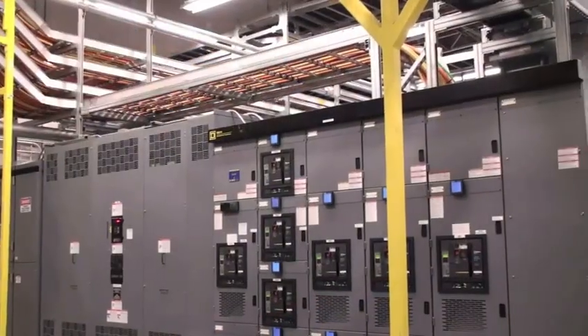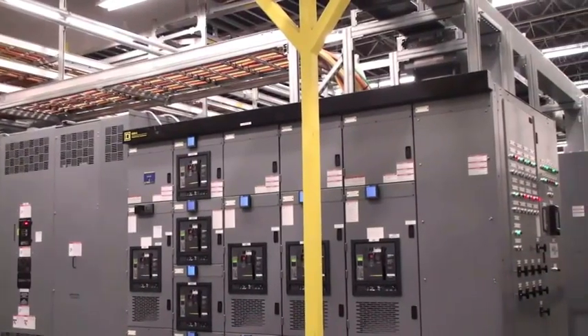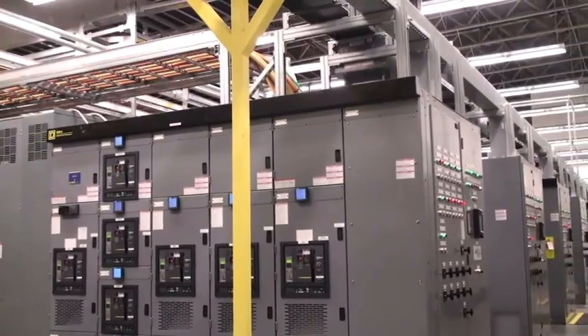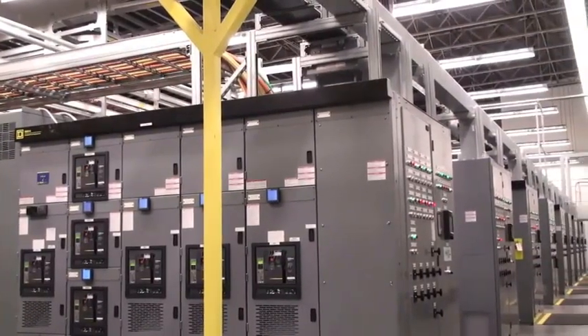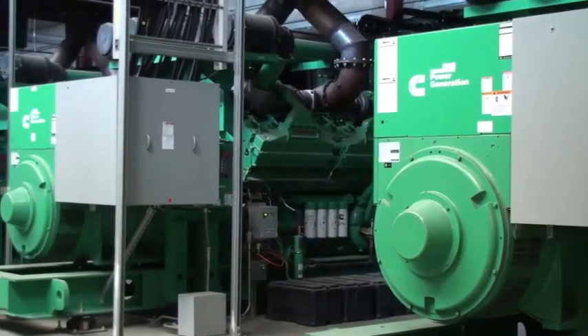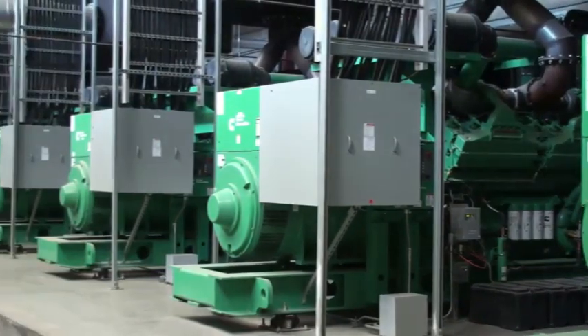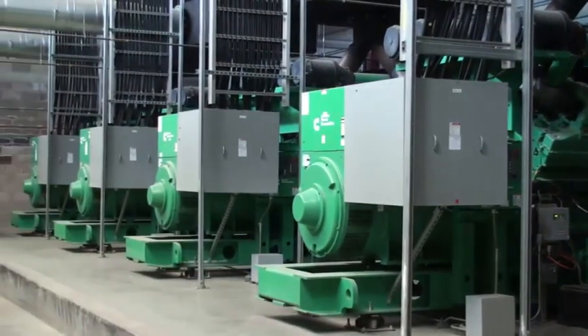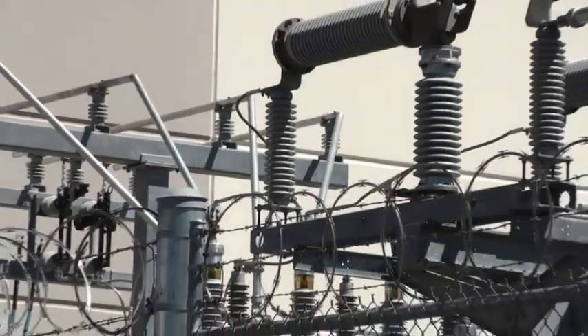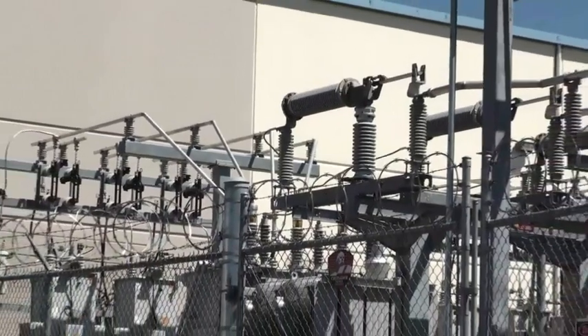The system is designed to ride out a utility power interruption for 6 seconds before its switching systems, 1 for each UPS, switch to generator power, a separate 2 megawatt generator for each switching system. The entire facility can be running off generators within a minute of the interruption. Once it is engaged, the data center runs off generator power for a minimum of 30 minutes past the last utility power interruption. Redundancy is vital to the power system, and RagingWire holds 2 engineering patents critical to its execution.